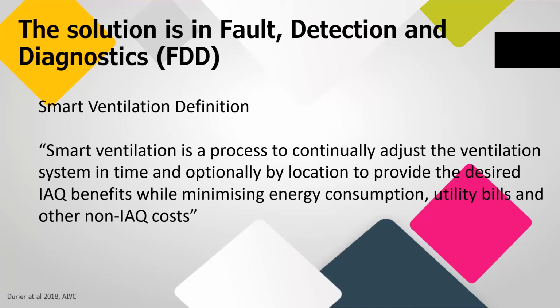So to address these challenges, we analyze through automation common building HVAC equipment by exporting work orders generated by your building energy management system, your BMS, and use this data mining to identify issues which are not the same as errors and faults that your BMS reports in a normally operating BMS.